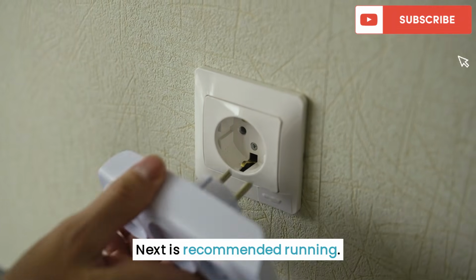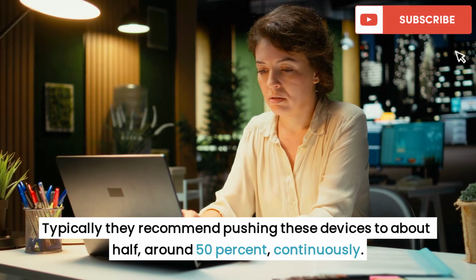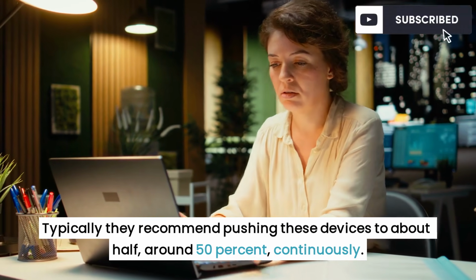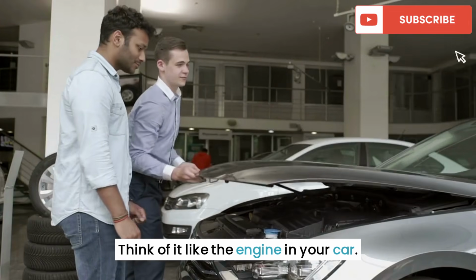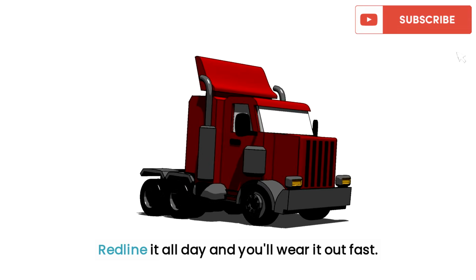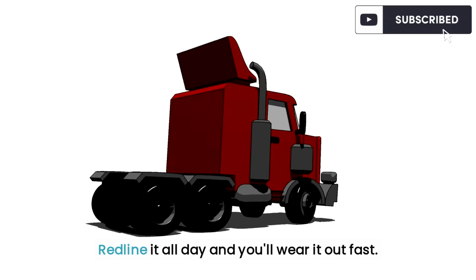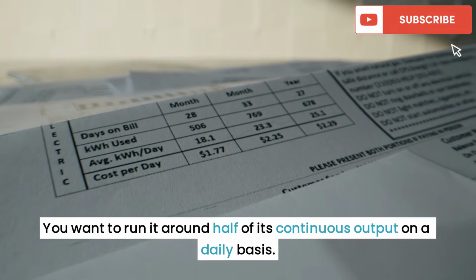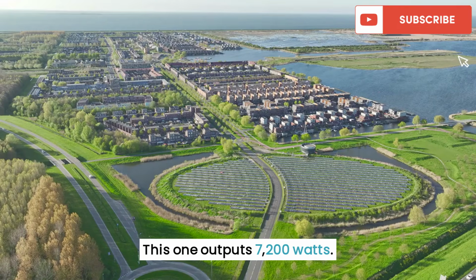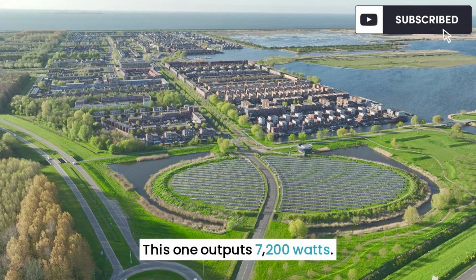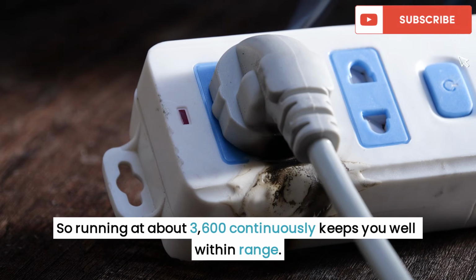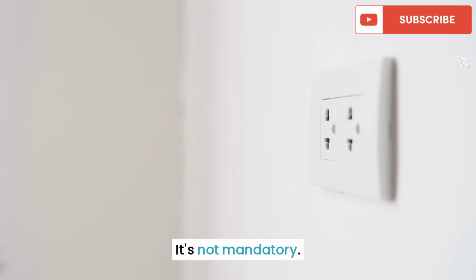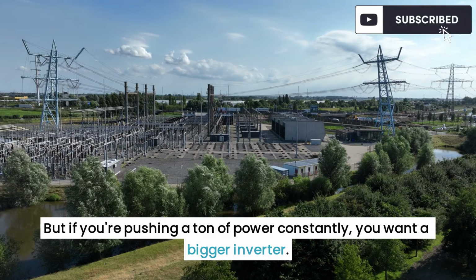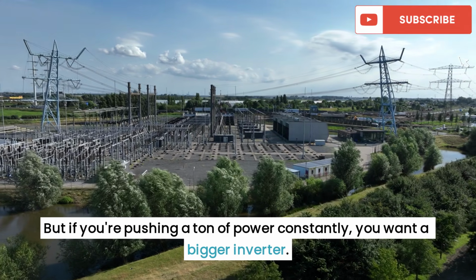Next is recommended running. Typically, they recommend pushing these devices to about half, around 50%, continuously. Think of it like the engine in your car. Redline it all day, and you'll wear it out fast. You want to run it around half of its continuous output on a daily basis. This one outputs 7200 watts, so running at about 3600 continuously keeps you well within range. That's a general rule of thumb. It's not mandatory, but if you're pushing a ton of power constantly, you want a bigger inverter.